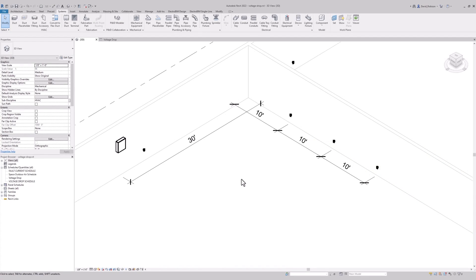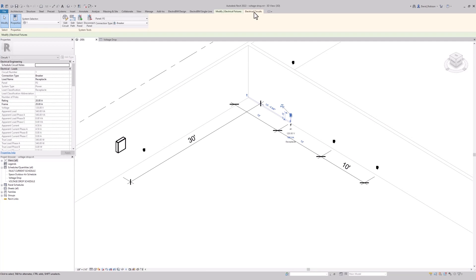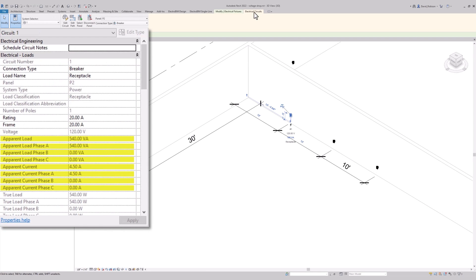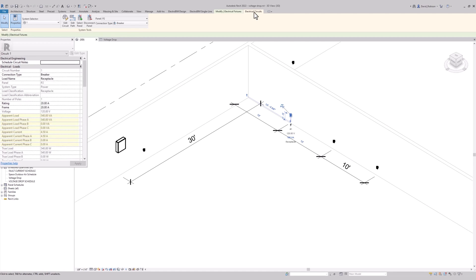I've got a very basic Revit project put together here, stripped down so we can focus on just the pieces relevant to voltage drop. Let's start by looking at the load on the circuits. When I select this circuit, it has an apparent load associated with it from the loads of all the receptacles on it. That's the load Revit is going to use for the voltage drop calculation. That's pretty straightforward, though it does cause some problems we'll see in a little bit.